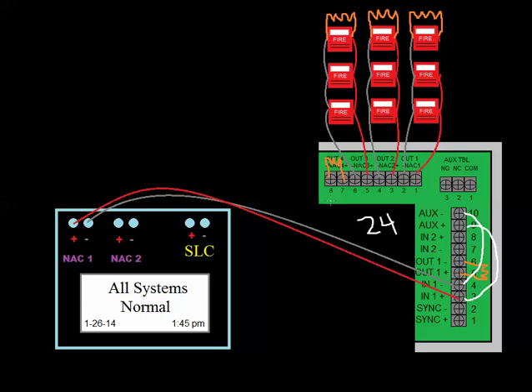The Notifier panels and the Fire-Lite, when they're in alarm, they still charge their batteries. But I've seen other manufacturers, like the Edwards power supply, which is a BPS. I found that when you configure those BPSs in that manner, they do not charge the batteries.